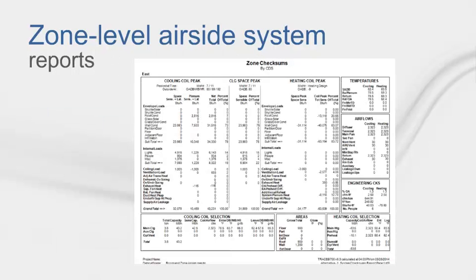After you have completed the rest of the model and calculated, you would want to look at the system component selection report or zone checksums report for coil and fan sizing information — not the room or system checksums. We do give you some coil sizing information, but it is up to you to select the coil you want. We give you the total tonnage and the delta T required, but we do not know the width, height, and fin spacing information to make a selection for you.